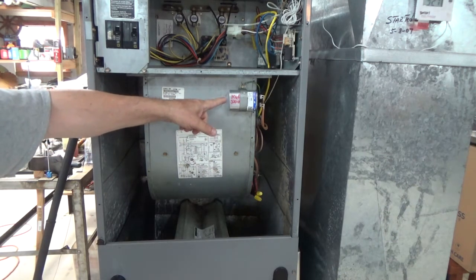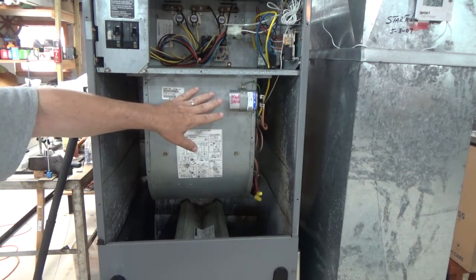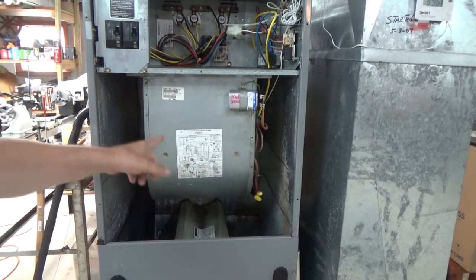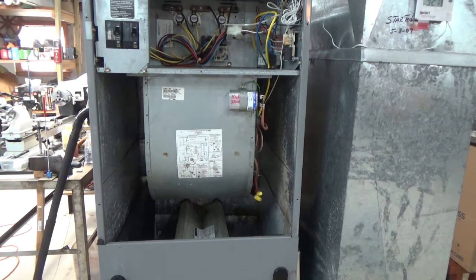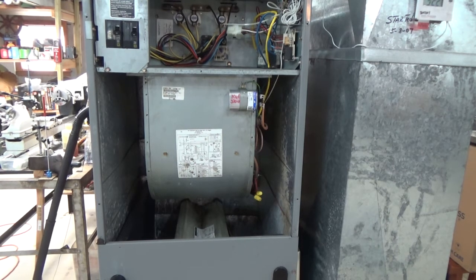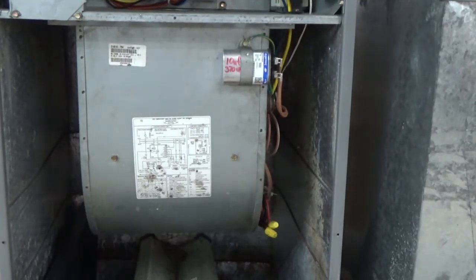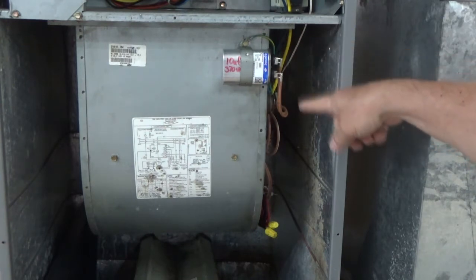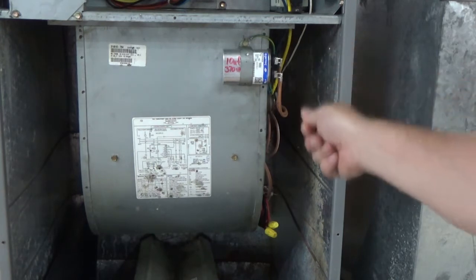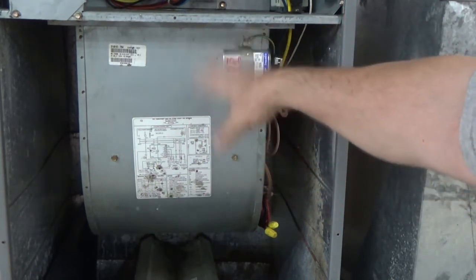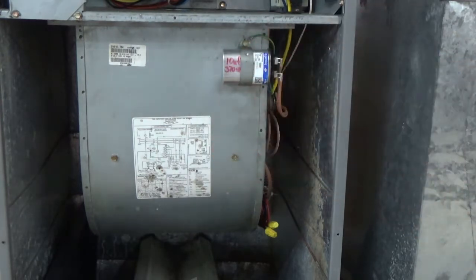What you want to notice is the start capacitor - that most likely still has a charge in it, so you really don't want to be touching the ends. However, you do want to examine it. In all my years of owning a home and dealing with HVAC systems, either at my house or other people's houses - I'm not a service technician, want to point that out. I've only had training, and I have a refrigerant card where I can legally buy refrigerant. Been to school, took the test. Anyway, what I want to point out is on the motor, the start capacitor is most likely still charged - you don't want to touch that. You can take a screwdriver and touch the two ends to discharge whatever current electrons are still in there if you want to, but the main thing is to look at it.